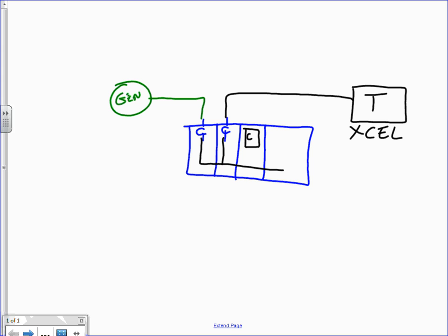We could walk that load onto the genset, and once the load is ramped onto the genset, bingo, it'll open up from the utility, and now I have all of my load on genset, and it was seamless to the downstream loads. They didn't see a hiccup. There were no gaps in that sine wave. Everything was smooth, and it kept things in full operation. So now I can stay on genset during the storm or during the peak control, and then at the end of that, I can just reverse it and then move the load back to the utility.